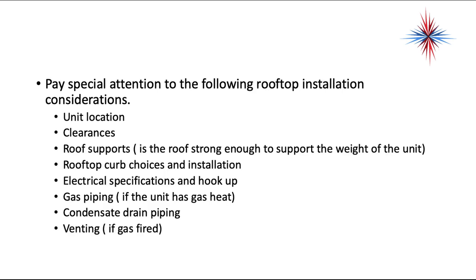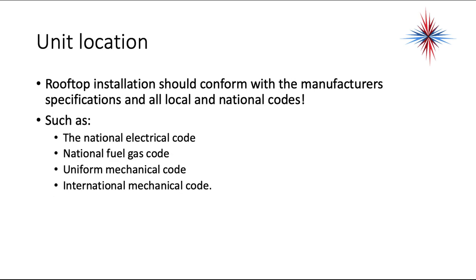Pay special attention to the following on rooftop installations: the unit locations, clearances. Roof support is extremely important. Is the roof strong enough to support the weight of the unit? Rooftop curb choices and installation, electrical specification and hookups, gas piping if the unit has gas heat, condensate drain piping, and venting. Rooftop installation needs to conform with manufacturer specification and all local and national codes.